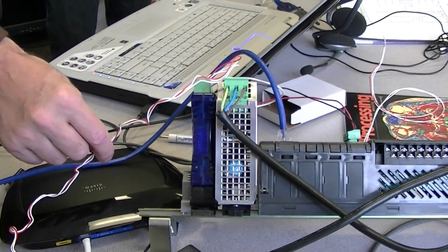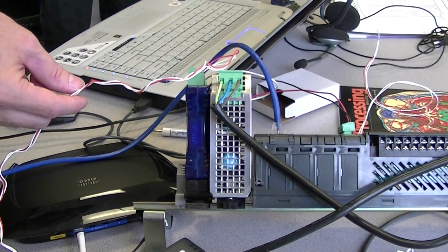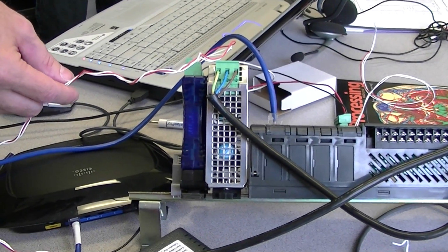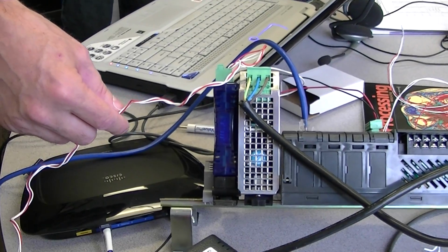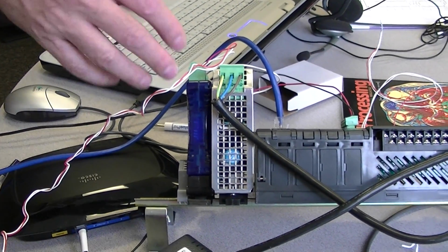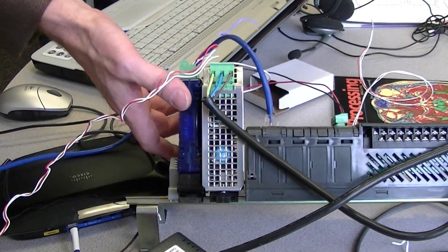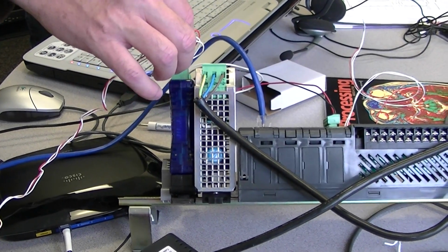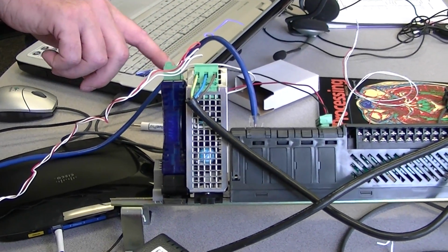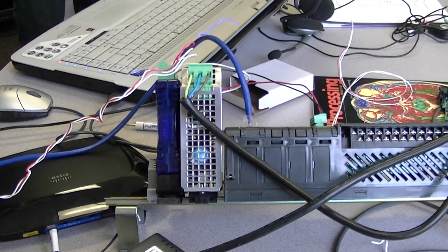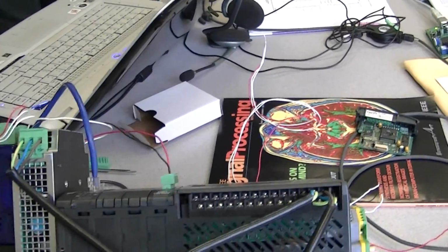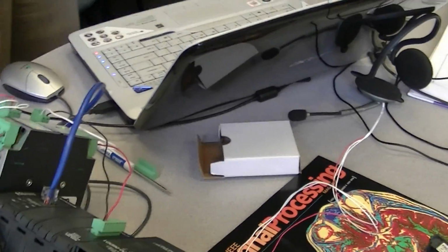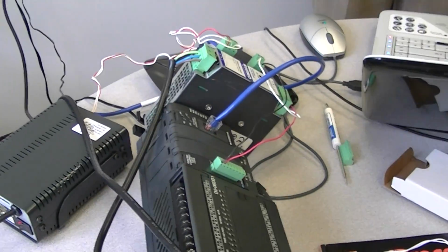Okay. So does this guy read temperature? No. It's an electronic device. It does voltage or current or something, but it's a very, very small amount of voltage, and that's not a good way to try to send it very far. So we have this little blue box here, which is called a transmitter. It will read this very tiny voltage in, and out through here, going over to the industrial computer here, it sends current. And this little card right here can detect how much current it is.